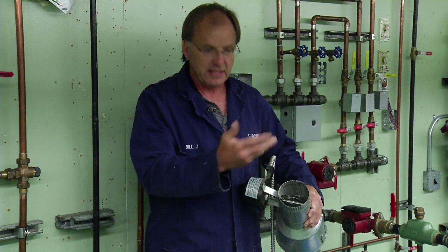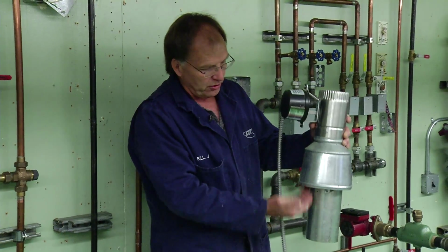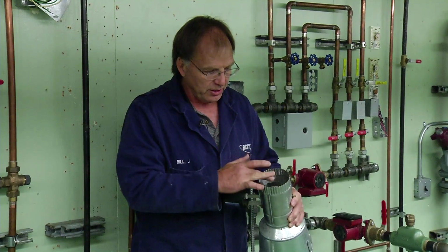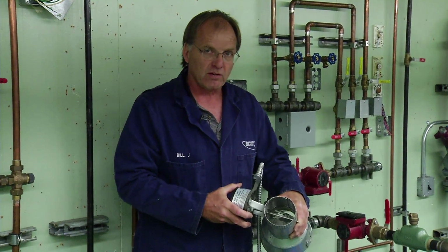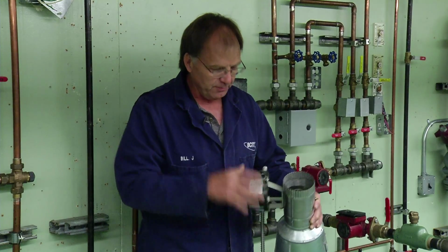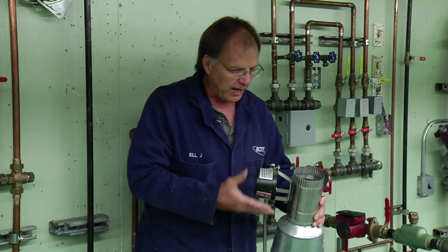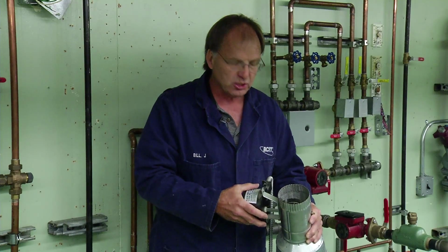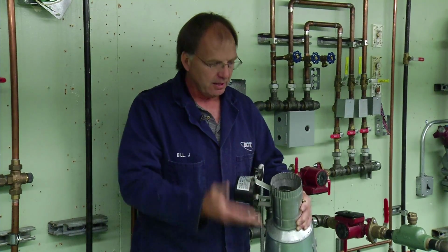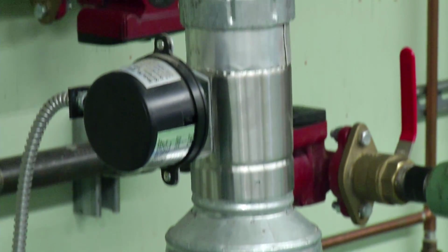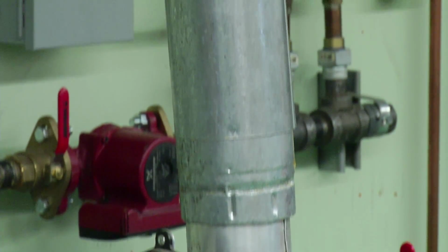That would allow vent gases to pass. It would also allow air to siphon up through the dilution air openings and therefore give us a heat loss. So this would be the position it'd be in when the boiler fires. When the boiler's finished and it's up to temperature, the motor will wind the valve closed, the damper closed, therefore blocking any further convection of the household air up to the outside.